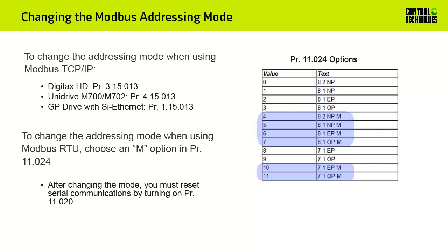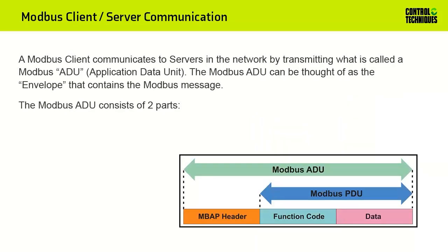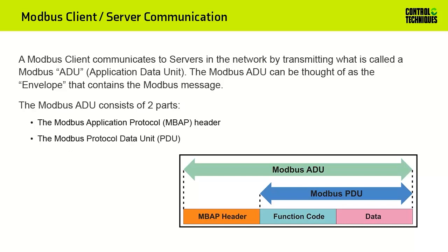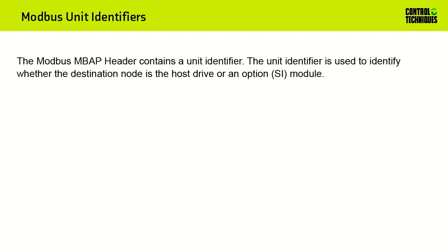A Modbus client communicates to servers in the network by transmitting what is called a Modbus ADU, or Application Data Unit. The Modbus ADU can be thought of as the envelope that contains the Modbus message. The Modbus ADU consists of two parts: the Modbus Application Protocol, or MBAP, header, and the Modbus Protocol Data Unit, or PDU. The Modbus MBAP header contains a unit identifier, which is used to identify whether the destination node is the host drive or an option module.